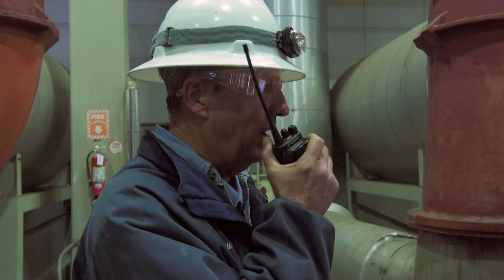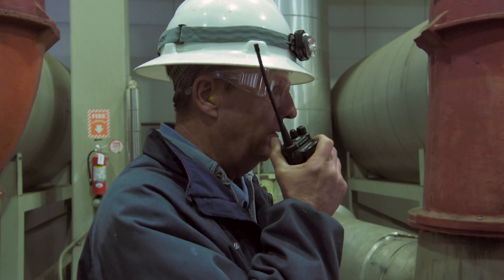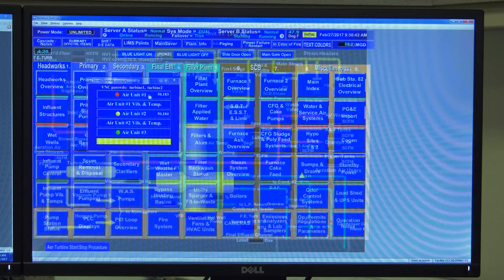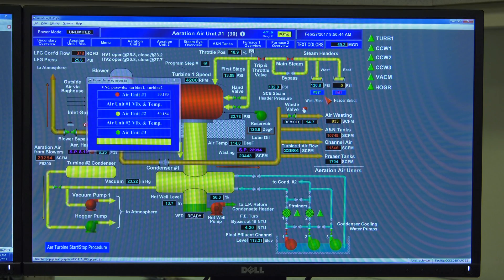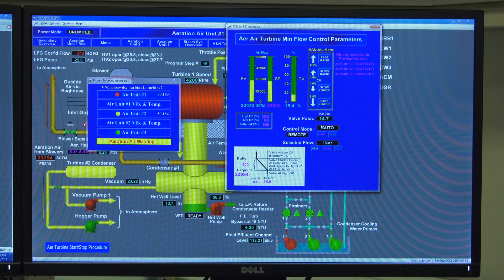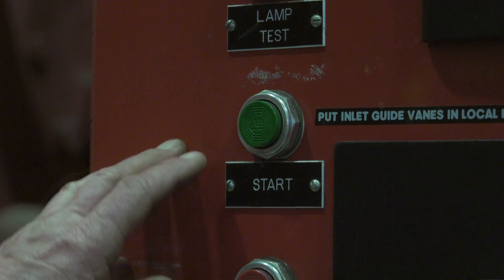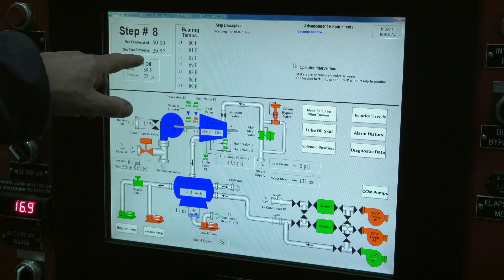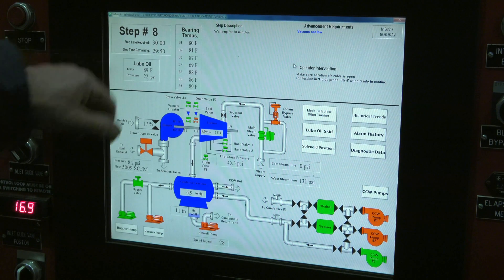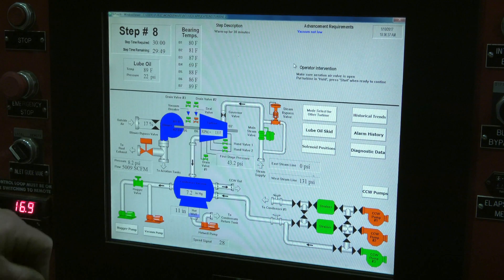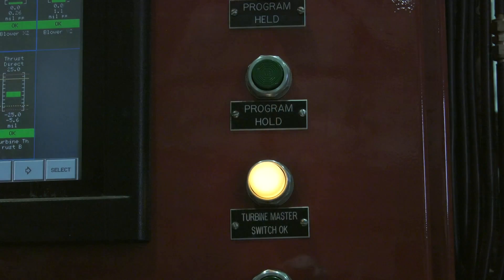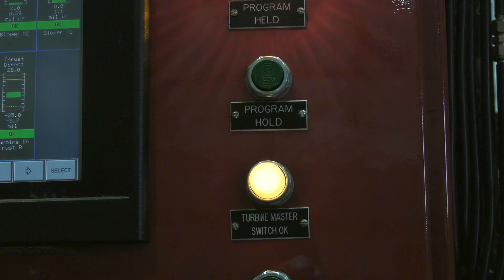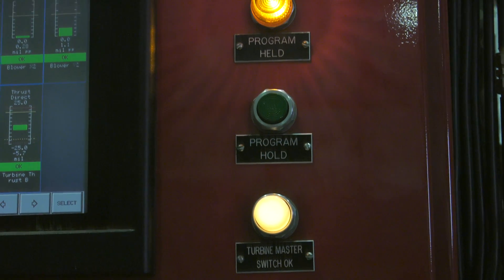Inform the shift supervisor and the solids control building that you will be starting the turbine. The shift supervisor will then take the air wasting valve off control. Now press start. The PLC will automatically step through to step 8 for a 30-minute warm-up. Press the hold button so the turbine doesn't automatically go online following the 30-minute warm-up.